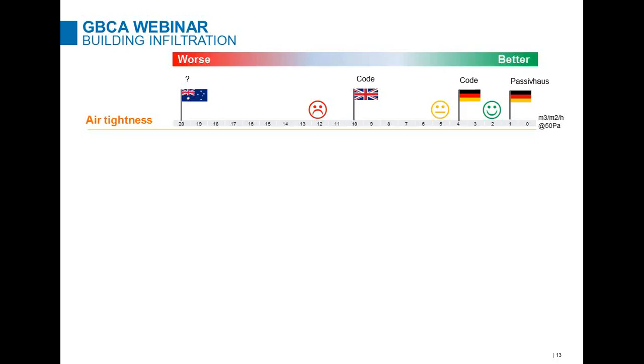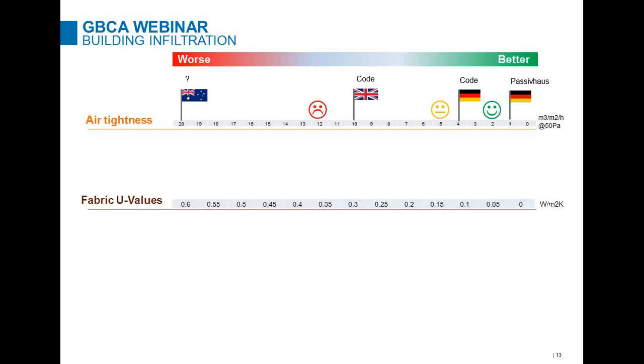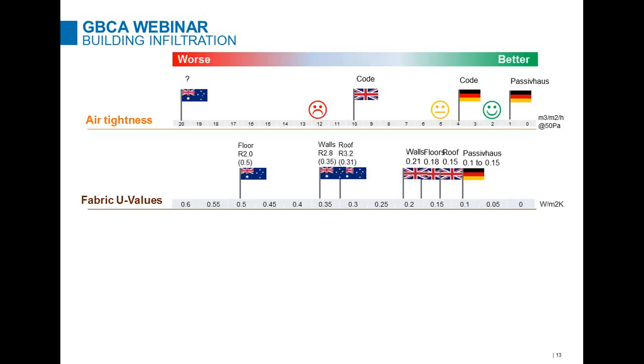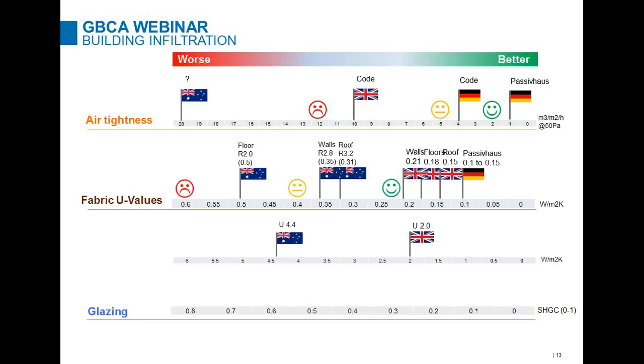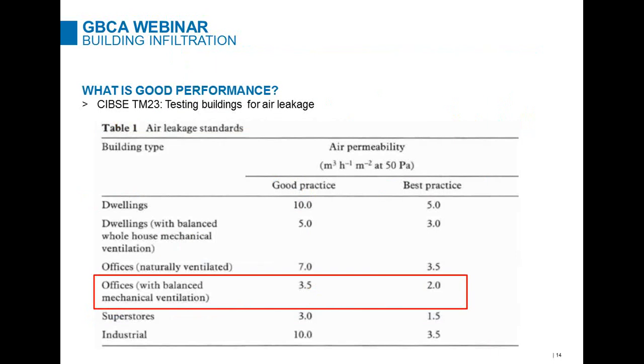Excellent is at 2 in a commercial building, good is at 5, anything worse than 10 is probably not very good. So you can see that if we're up around, I don't know, 15, 20, then we're really not in line with good practice internationally. And I've done that same thing for fabric U values and glazing, both in terms of the glazing U value and the solar heat gain coefficient, but I won't dwell on those two things because the rest of the fabric is not really the focus of today.